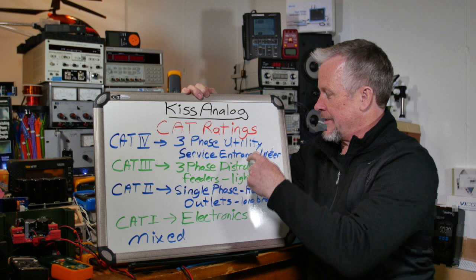Another thing I didn't really talk about, well, voltage isolation, batteries. When you open it up and you see the battery in its own compartment, that's great. When you see the fuses in their own compartment, great. If they're not the high rupture capacity, you know, with UL listing, still might be great. It's hard to say. If it's a category 4, well, I expect to see it. If it's category 3 or below, maybe not. Maybe it's not needed. Maybe it's not as important.